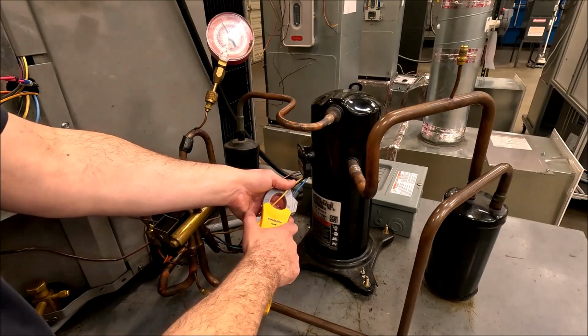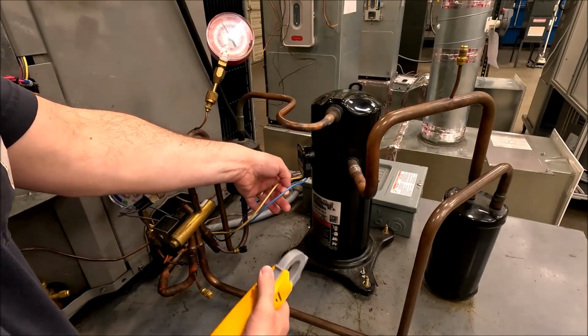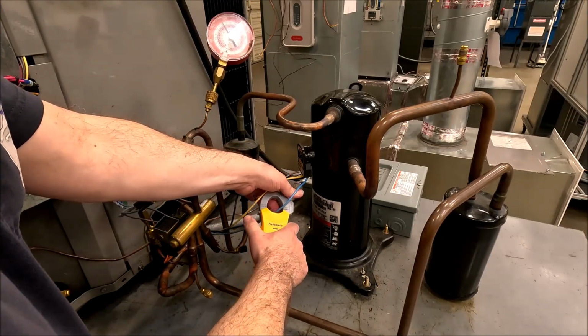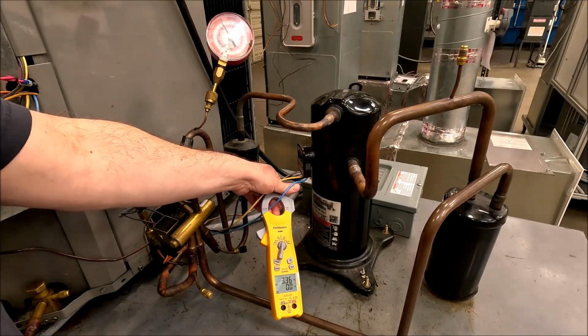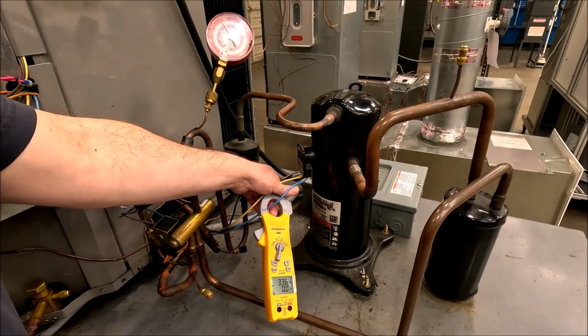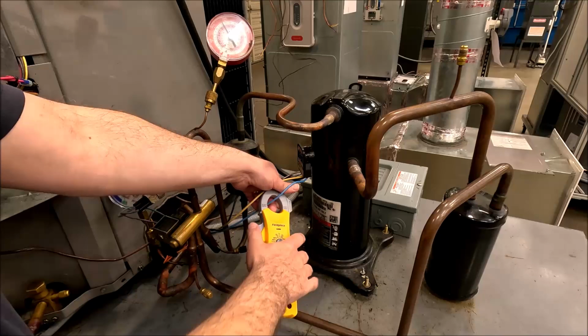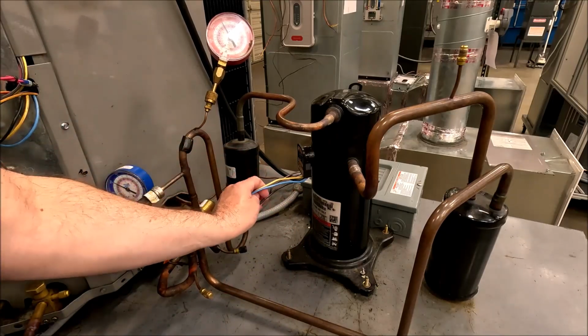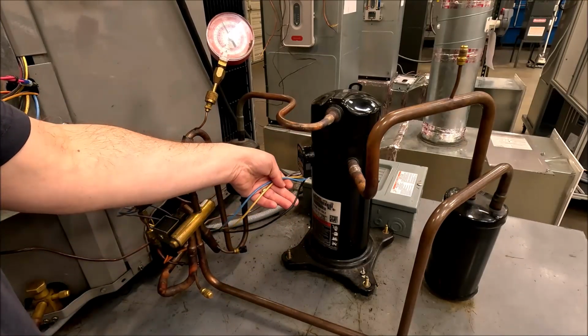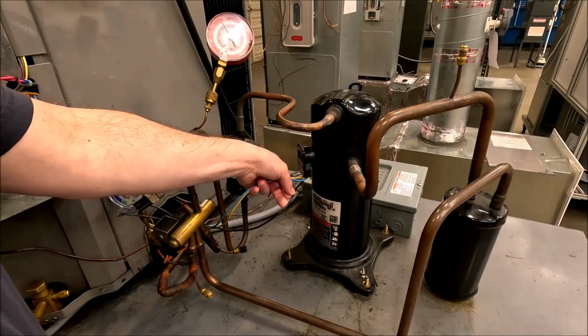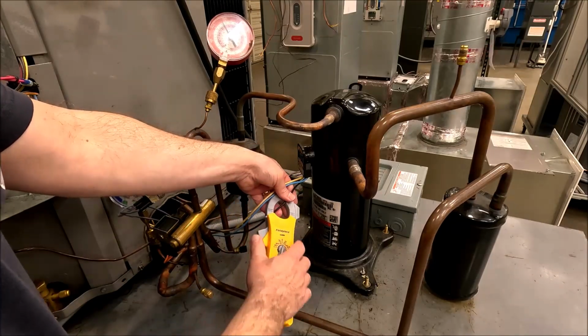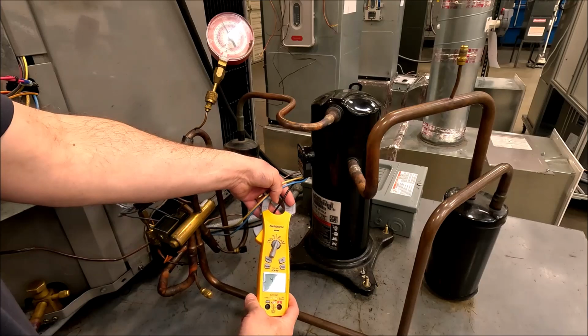3.1 amps. The other load in this motor is the start, so let's check it. 3.35. So what's your amp draw? 3.1, 3.35. Since it's 2 independent loads, do they add up? Watch what happens with electricity on the one way out, the common terminal, going back to the other side of power. 4.85.